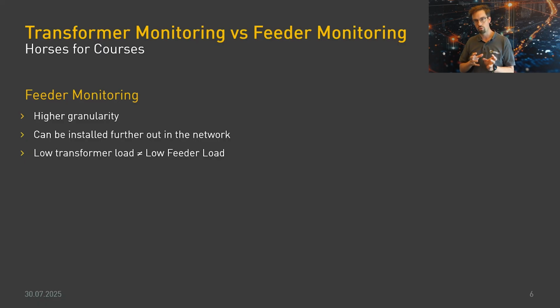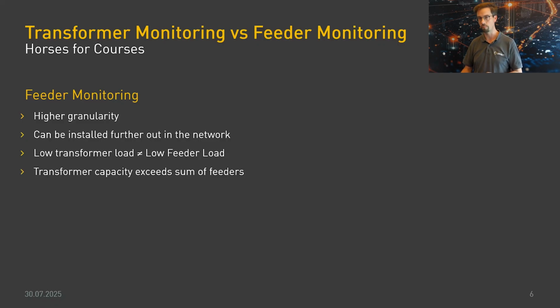Next, it's important to bear in mind, people get mixed up with this, that just because I have a low transformer load doesn't mean I have a low feeder load. So you can imagine a situation where I have a transformer that's maybe sitting at 30–40% of its capacity. That would be something you wouldn't be worried about at all. But all of that load could be sitting on 1 or 2 feeders, and those feeders could well be outside of their capacity or very close to their capacity. So if you come from a background of monitoring transformers and you think you've got a good overview of what's happening, it could give you a false sense of security without having the feeder level data. So in those situations, especially with more feeders, it's really important to be able to understand what's happening at the feeder level, because your transformer just simply can't tell you that.